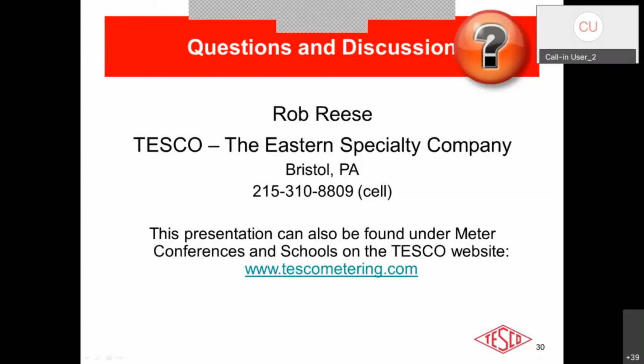First and foremost, like I said, magnetized CTs. CTs can be magnetized due to a number of reasons: lightning strikes, temporary open secondaries, harmonics on the line. If you have a fluctuating customer load, the CT can automatically pull itself out of that magnetized state. But if you have a constant customer load, it can stay in that state indefinitely. So first and foremost, look for a magnetized CT.